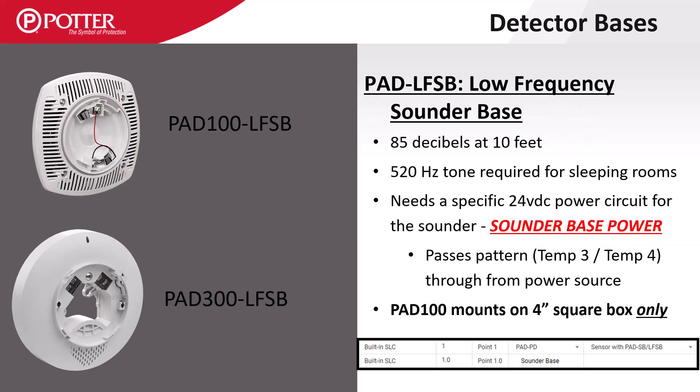The PAD LFSB is a 520Hz version of the sounder base. The 100 series LFSB can only mount on a 4 square box since it recesses back into the box, while the 300 series has several mounting options since it has no protrusion.